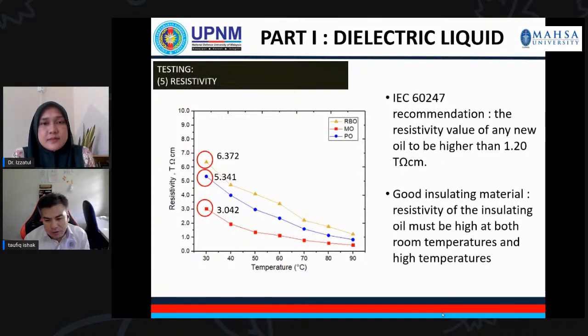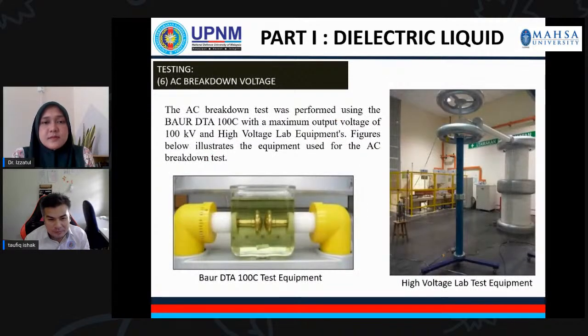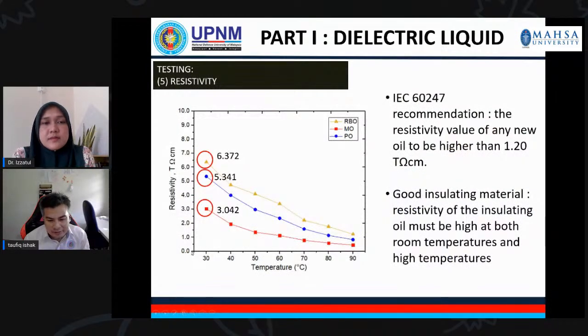As you know, the resistivity will decrease as the temperature increases. As you can see from the graph, the rice bran oil and also the palm oil have higher resistivity as compared to mineral oil. At 30 degrees C, based on the standard, the rice bran oil has 6.372 tera ohm centimeter, which is 2 times higher than mineral oil, which is around 3.042 tera ohm centimeter.